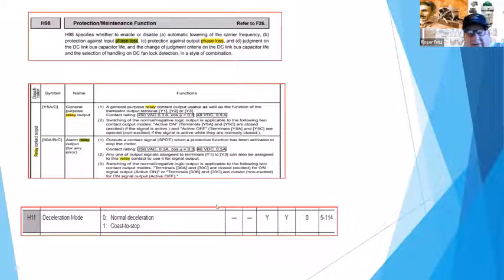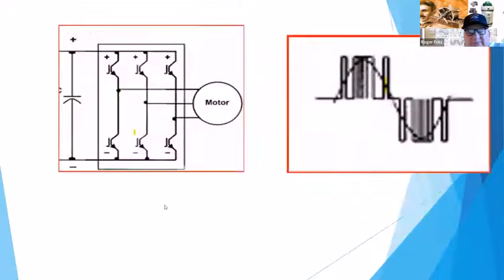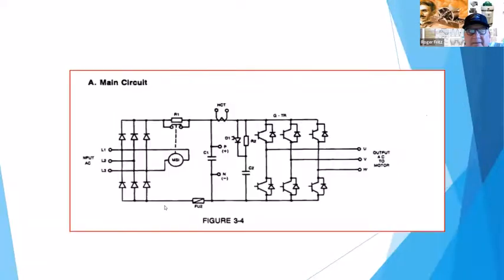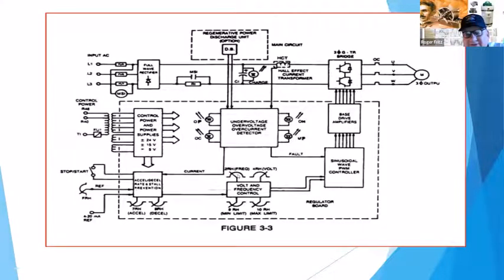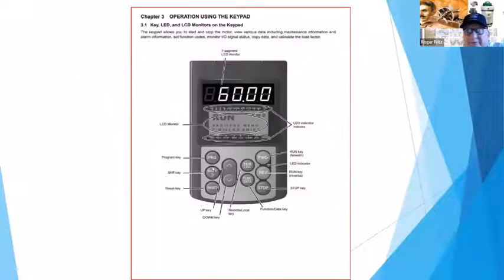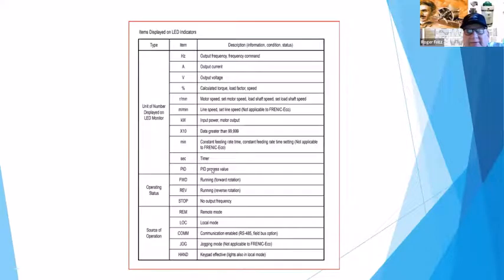And so the other is you can also set, again, you have to find parameter H11. It's the deceleration mode. So you can set whether you want it to coast to stop or normal deceleration, ramping it down. Again, it's all the way back to what I was doing 40 years ago with these various potentiometers, those accelerations, decelerations, upper limits, all that's done. All that's just been done. A lot of this has been redone, put a microprocessor on the front end side, and then it can jump through hoops and make the motor run forward, backwards, exactly to a specific point.